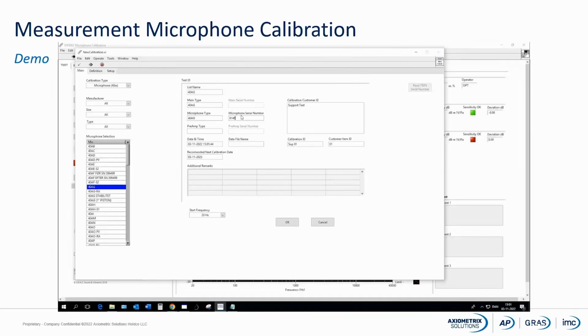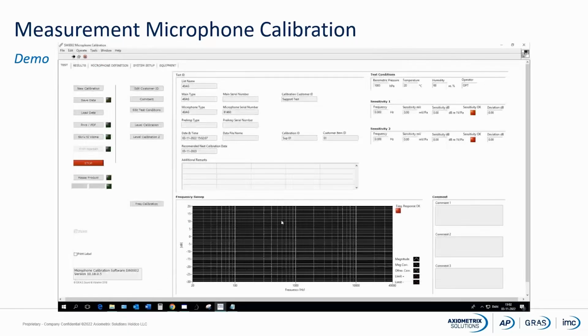I will start by putting in the serial number for my microphone. It's done there. Then I can put in the calibration ID, the customer, and the customer number. I also have to tell the system at which frequency I will start. I would like to start from 20 hertz. So that is done. Now we can see we have the test conditions in the system. We also have all the data for the microphone we are going to calibrate.